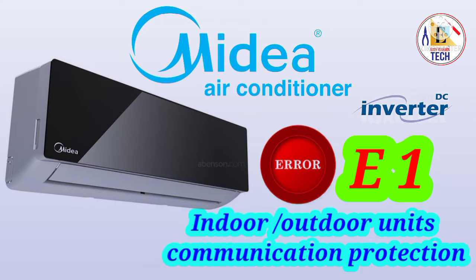When you see the error E1 in your Midea air conditioning, it means indoor-outdoor communication failure. When the communication between our indoor unit and the outdoor unit is not properly done, at that time we get this error. The first cause is the cable between indoor and outdoor. First you have to check the indoor and outdoor cable, if it is properly connected in the indoor as well as in the outdoor unit. If it is properly connected, then you have to check the continuity of your cable.